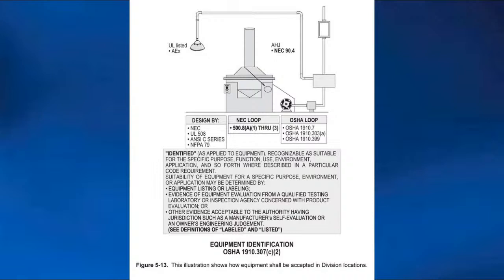All I'm pointing out here is that to approve this equipment, you're going to go to 500.8A1. One of the biggies there is that under engineering owner supervision, this equipment could be accepted by the authority having jurisdiction just by reading the control drawings and diagrams that come with it, to make sure all the components meet an installation dealing with an assembly.